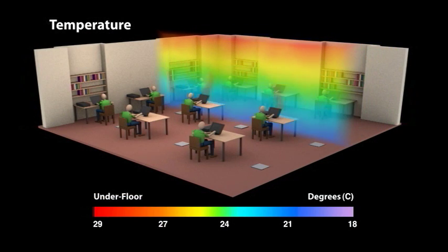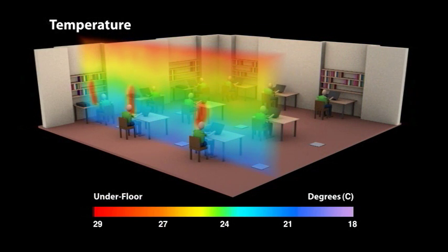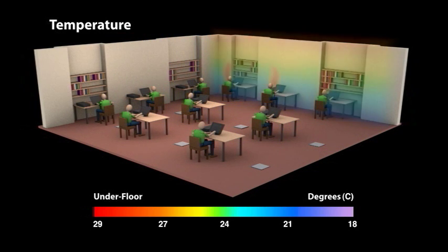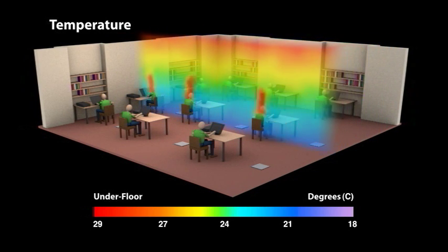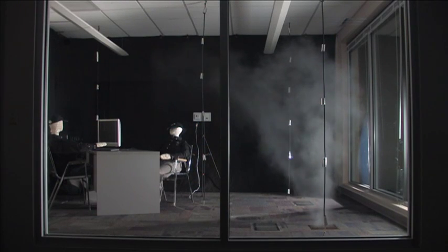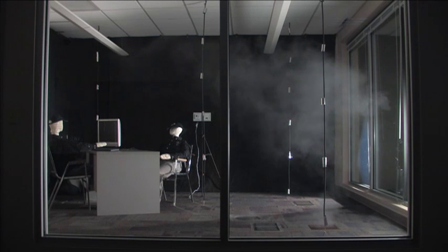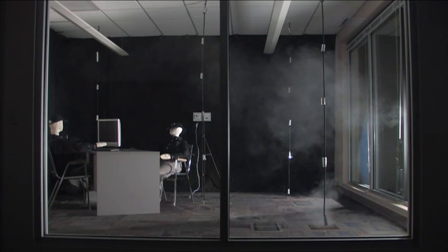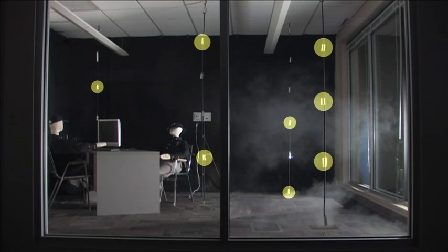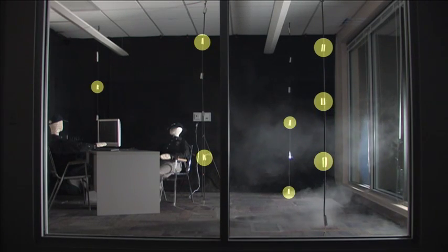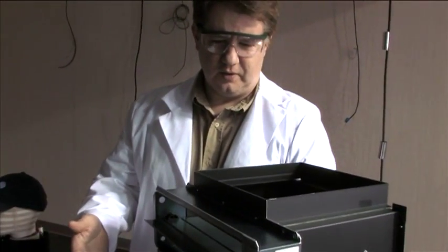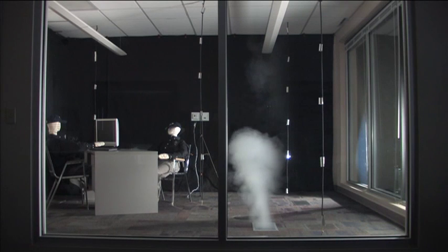Our diffusers are designed to throw conditioned air throughout the breathing zone, but not too high so that beneficial stratification can still be maintained. We measure success not just by diffuser throw patterns, but by the end result, effective 3-dimensional temperature control. By monitoring temperatures at different heights and at different locations in a floor plate, we directly measure effectiveness and optimize diffuser designs.